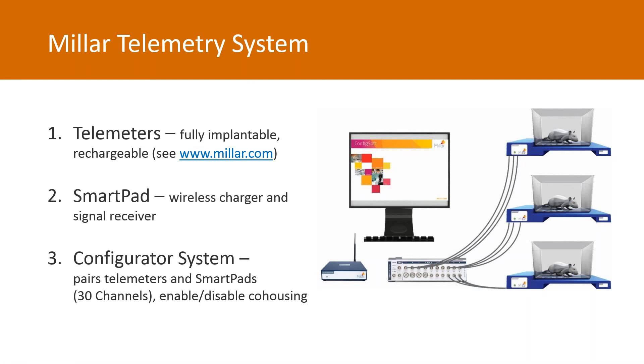In the Millar system, each telemeter is set on any one of 30 distinct data transmission frequencies, which we call channels. Having channels prevents interference between setups without the need for shielding. Each implanted rat in its cage is then housed on top of a smart pad set to the same channel. Smart pads are receivers for the biological data sent by the telemeters, and having 30 channels means a lab can run up to 30 telemetry setups at any one time.